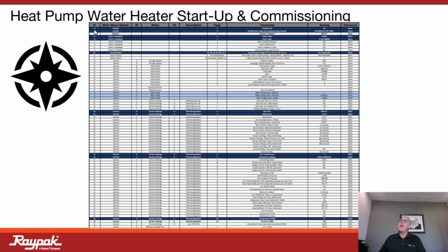So here's how you navigate to that A menu, the master menu. You program down to these individual parameters with that up and down. Some of these are password protected. Some of these are not password protected. So you'll have to enter this code based on the parameter you want to access, and that will then allow you to make those necessary changes. I completely understand this is a lot of information, but you're not going to need to navigate to each and every one of these parameters. Very few, in fact, will you need to navigate to. In a lighter blue, there's only 3 programmable features if you're navigating to adjust a BMS. If you're going to add a BMS communication, there's very few programmable features that you'll have to navigate to.